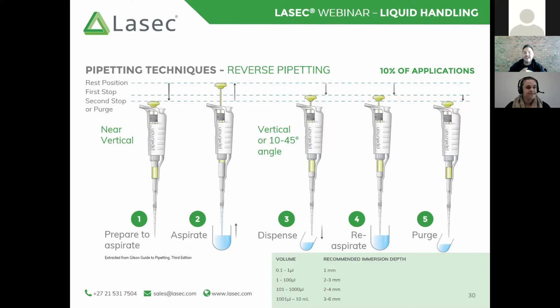The only other area where reverse pipetting is generally employed is if you're working with solutions that tend to foam or bubble. With a forward dispensing method, in order to get all of that solution out of the tip, you need to follow through to the purge step. Like I said, this purge step is just an additional amount of air inside the pipette that blows out whatever liquid is remaining. Obviously, in blowing that liquid out, you now introduce air into whatever it is that you have pipetted, and that can cause bubbles or foaming to take place.